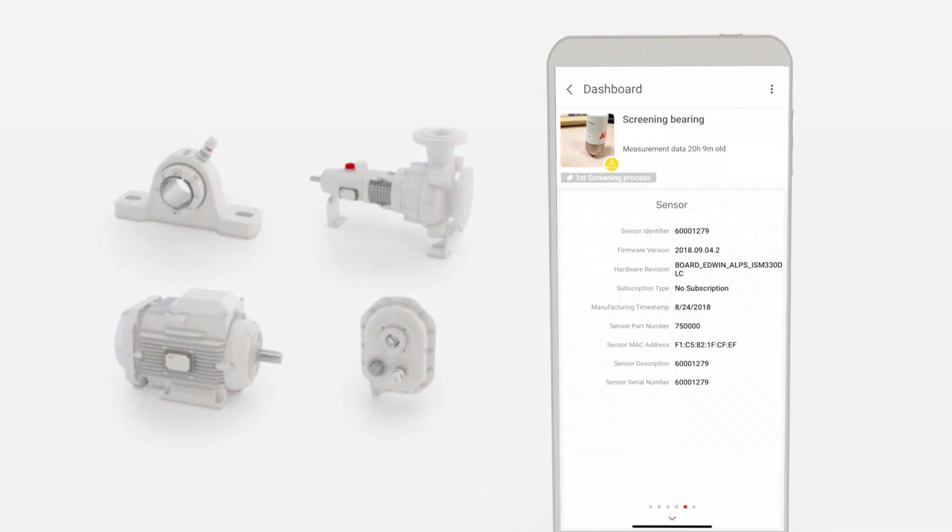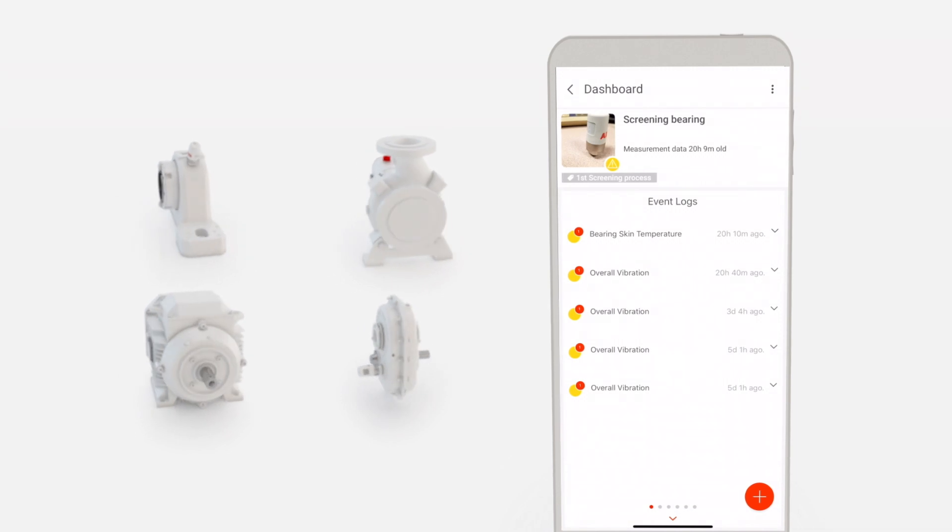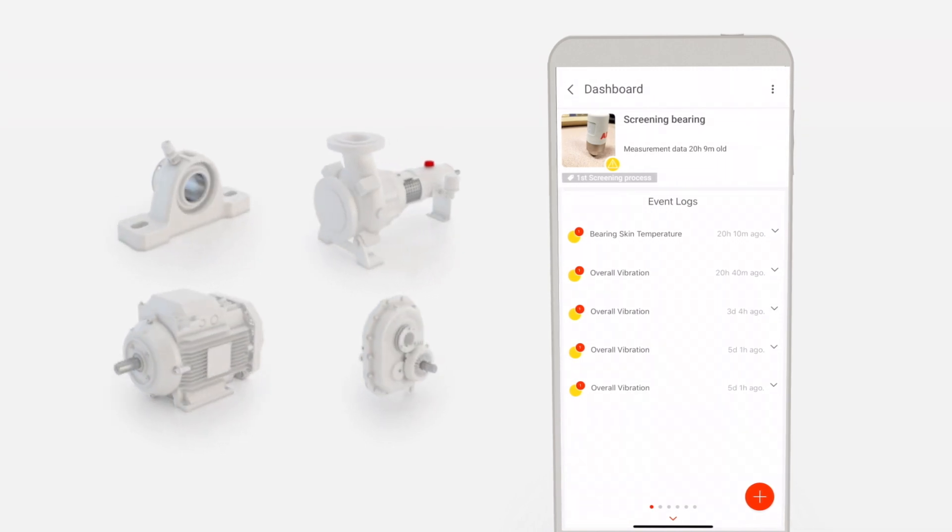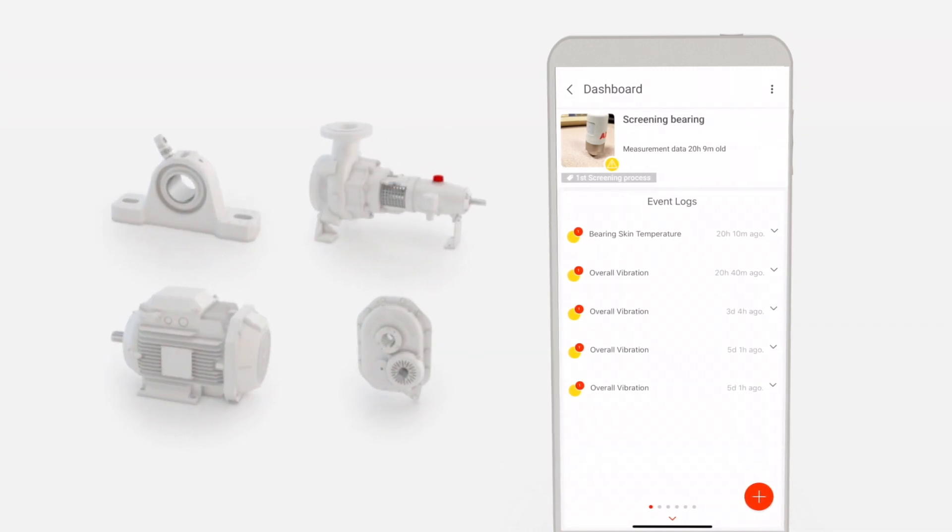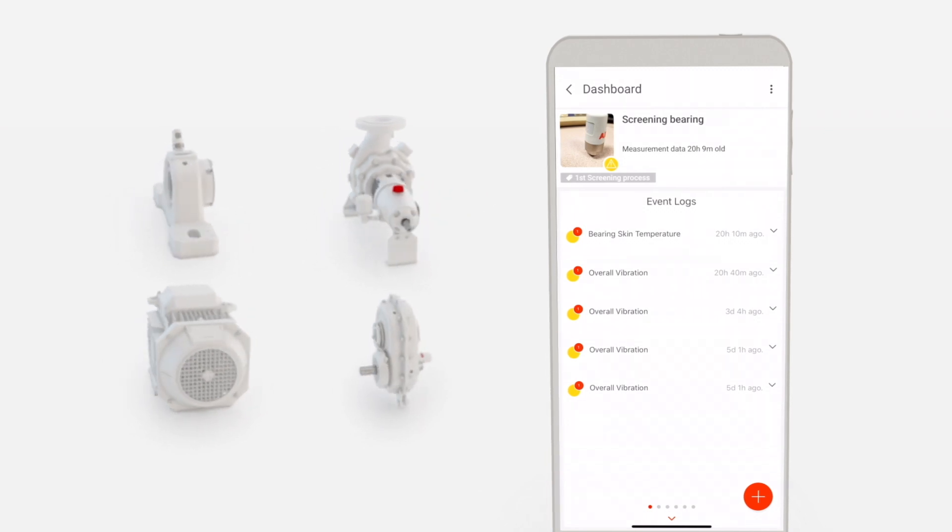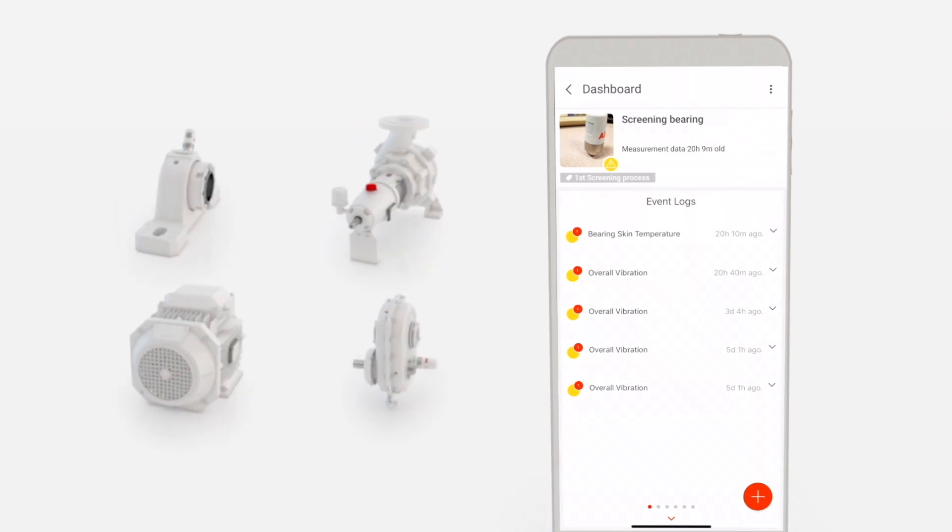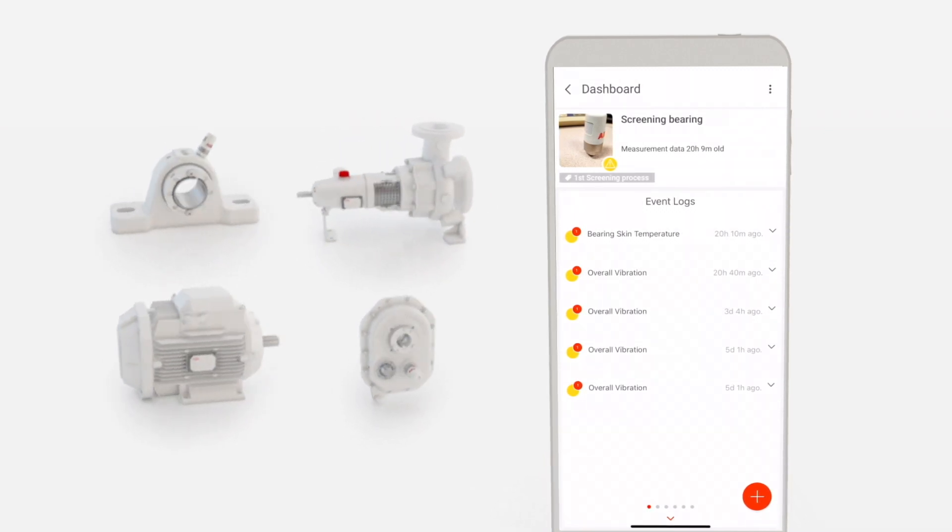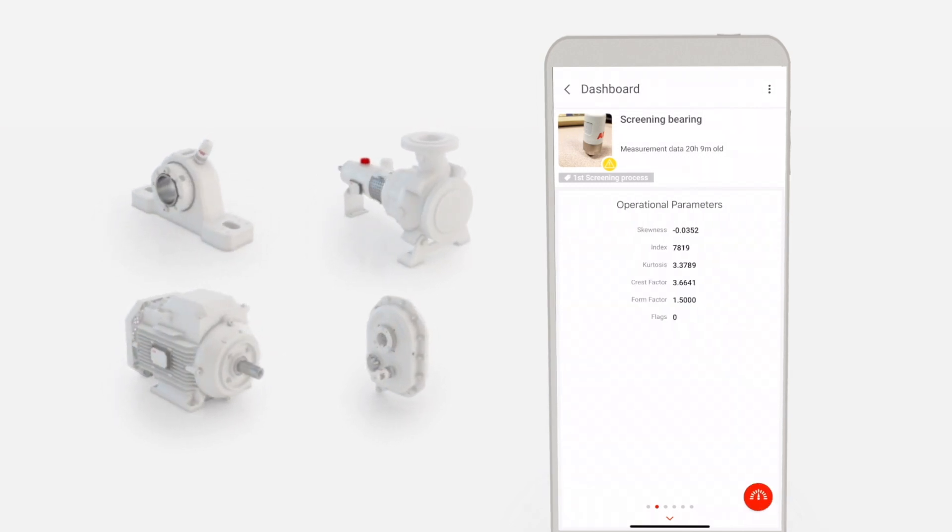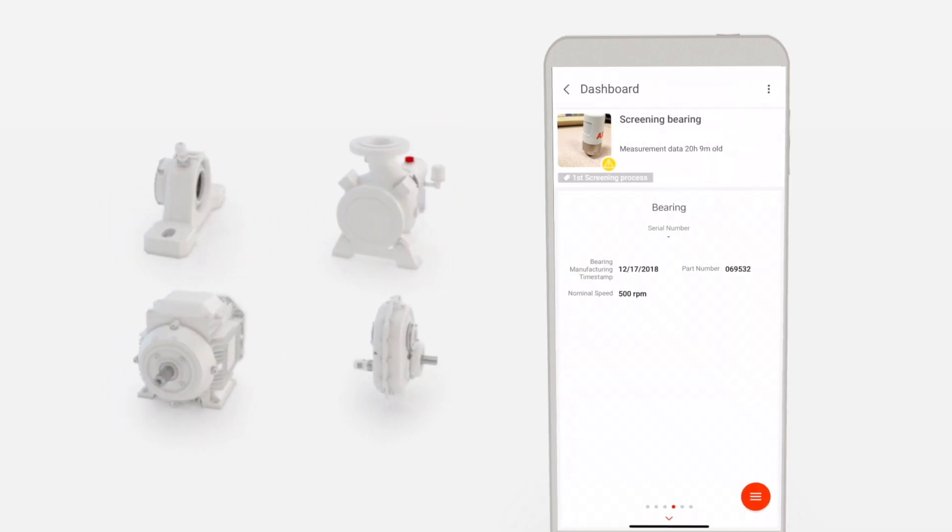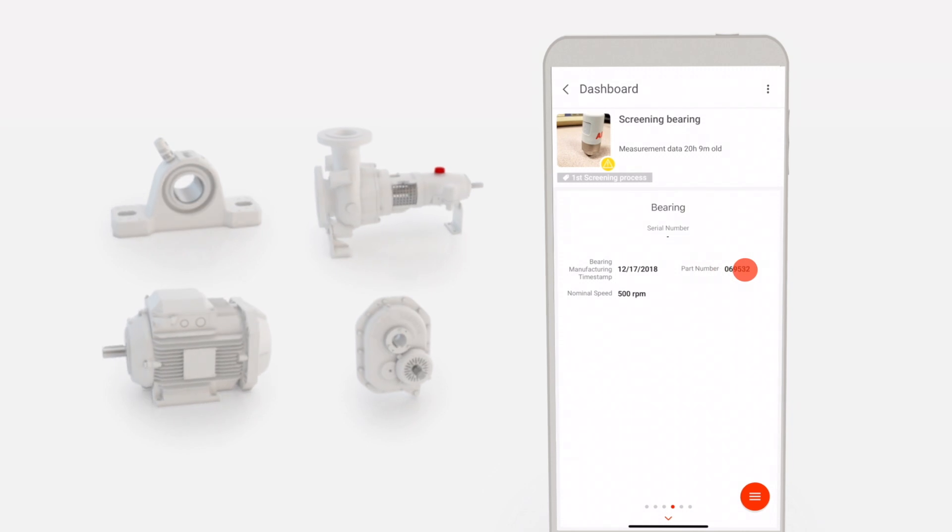If an asset shows an alarm for vibration, additional analysis is needed. Following further investigation, the user may decide a replacement bearing is needed. For example, swiping right will display the part number for ordering the replacement.